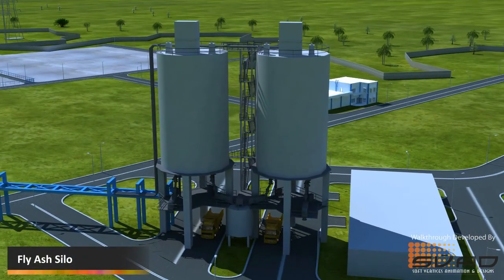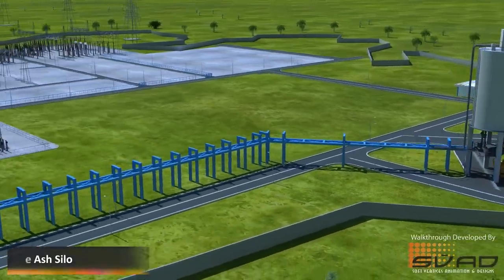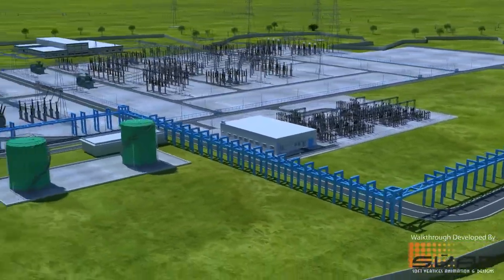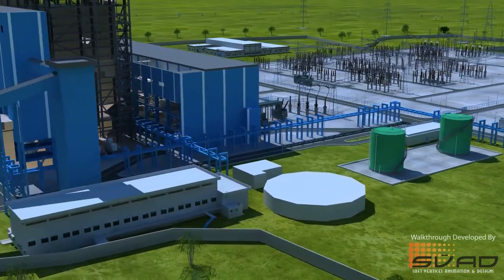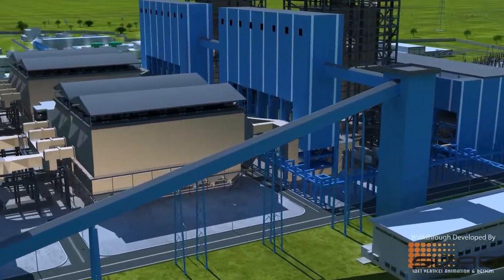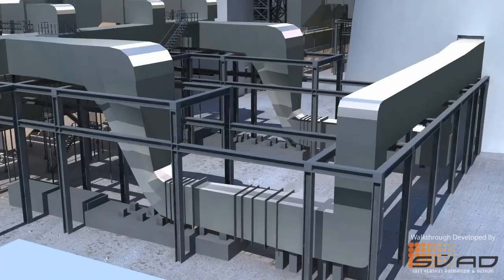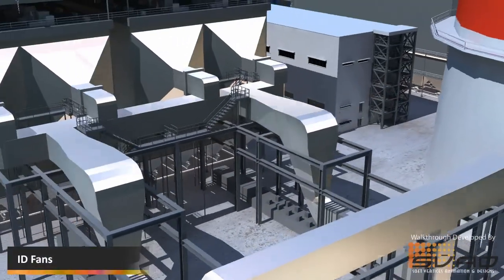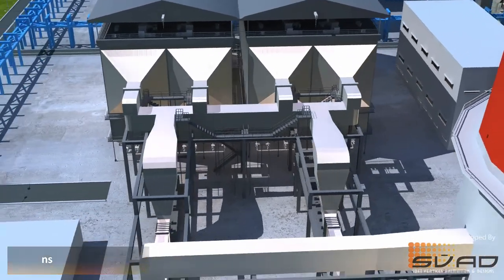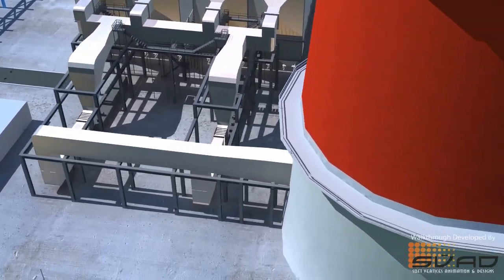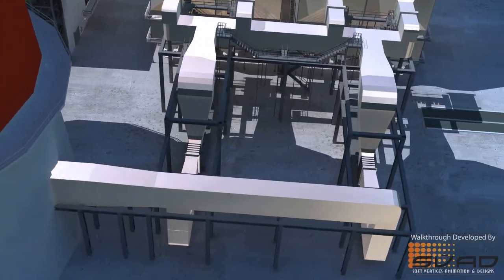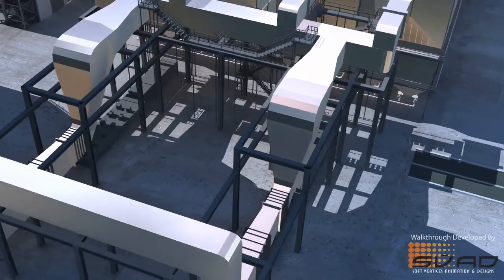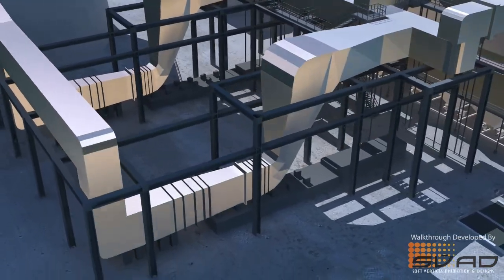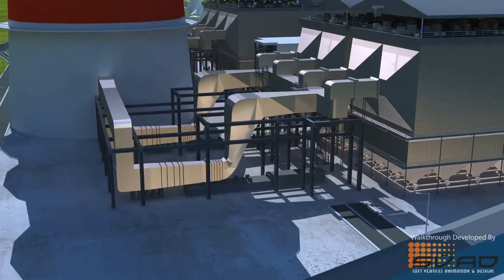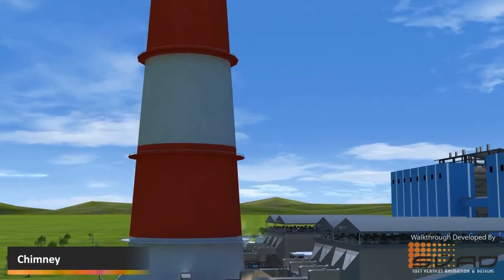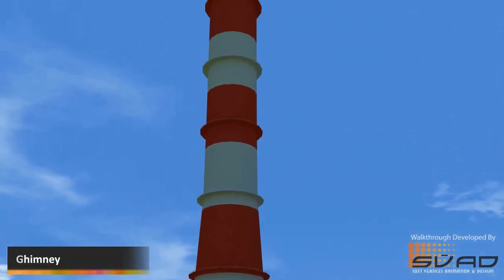Fly ash silo captures and periodically removes ash from the flue gas from ESP or fabric bag filters located at the outlet of the furnace before the ID fan and from the collection hoppers below the precipitators. ID fan is provided at the outlet of the boiler, that is, just before the chimneys, to evacuate the combustion product from the boiler furnace through the superheater by creating sufficient negative pressure to establish a slight suction in the furnace and discharge the gases into the chimney. Chimney is a structure to ventilate hot flue gases or smoke from a boiler or furnace to the atmosphere.